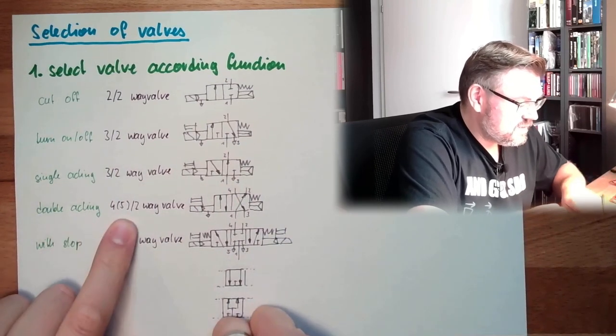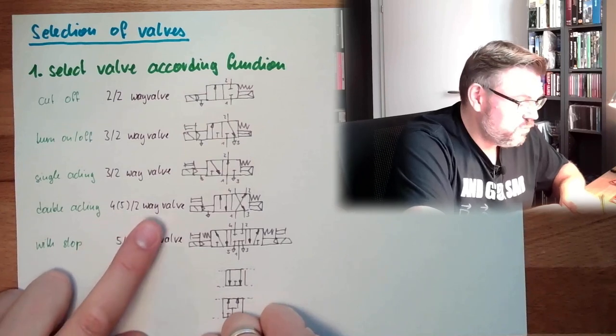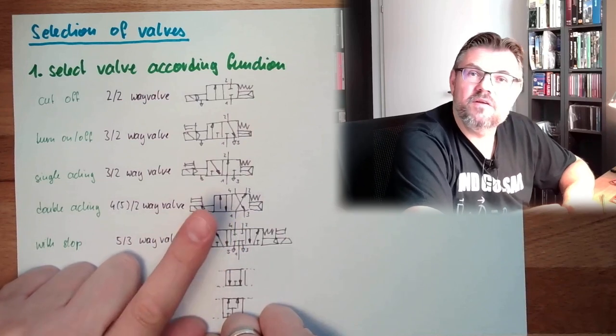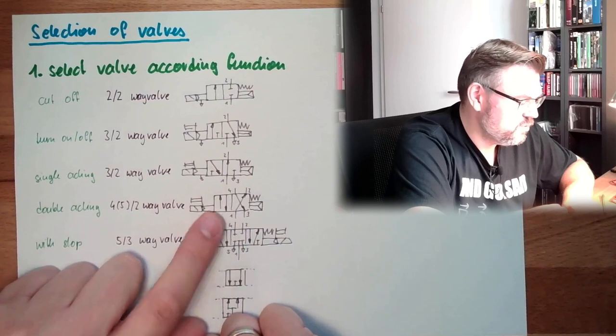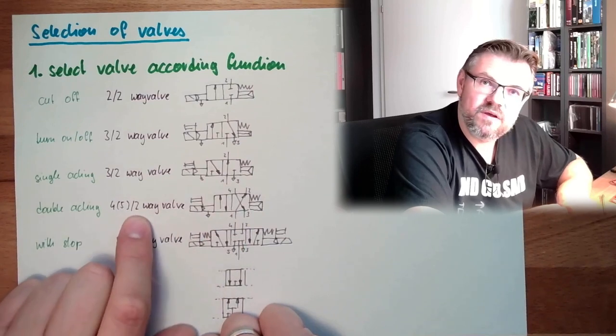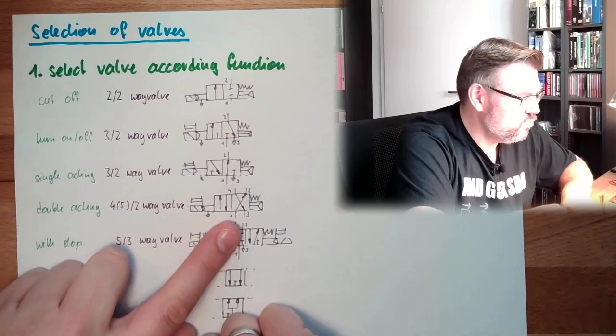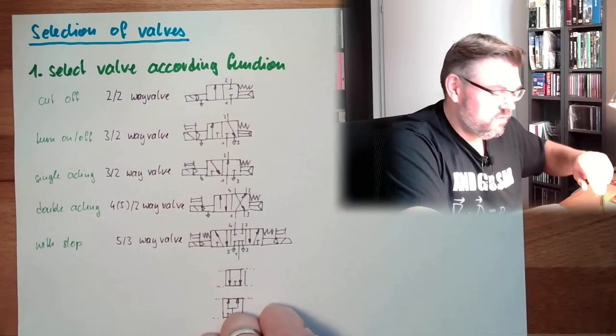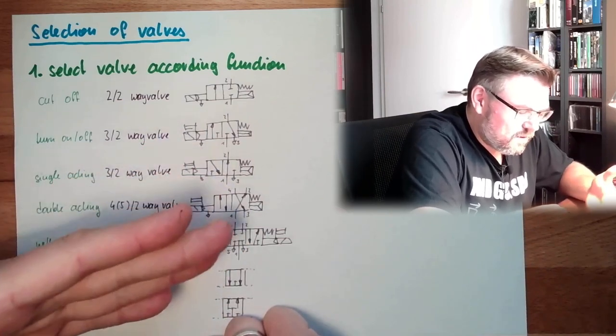Then double-acting cylinders, we said we are using 4 or 5/2 way valves. Here I have drawn a 4/2 way valve, this is very usual in hydraulics we have said. In pneumatics we usually have 5/2 way valves, because simply cheaper to produce and I can get rid of the air at the valve. We talked about this.